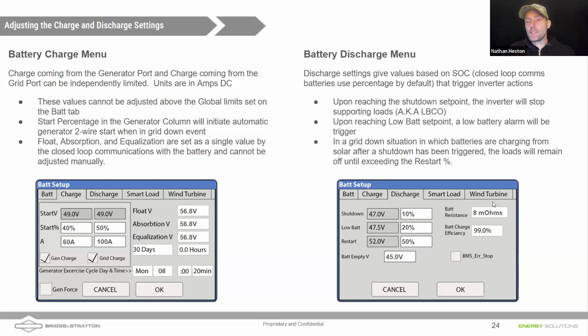Battery resistance. This is the resistance of the entire bank. For our batteries, it should be 24 milliohms divided by the number of batteries you have, because they're paralleling these batteries. The resistance goes down the more batteries you have. The battery charge efficiency, we'll set that right at 99%. These are very efficient batteries.